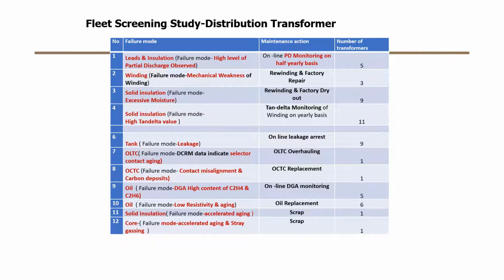When there is a short circuit fault, we're lucky if that fault was sustained for a very low duration, 80 or 60 milliseconds. But because I come from a background where I operated a short circuit lab for 10 years, I know that even a 10 millisecond fault is more than sufficient to damage your insulation and winding, because that is the peak of the fault.